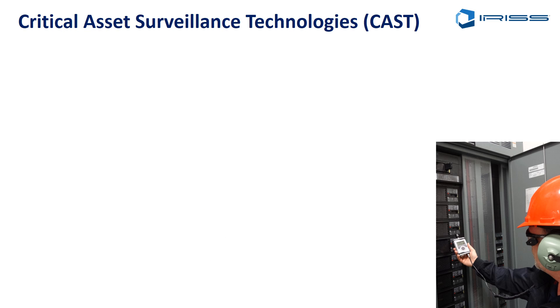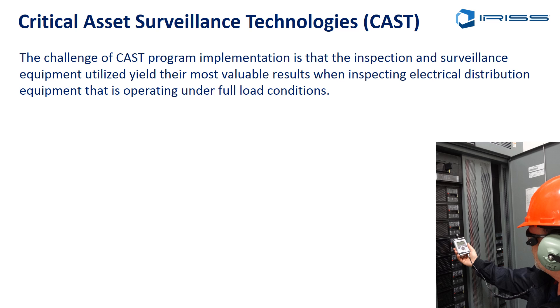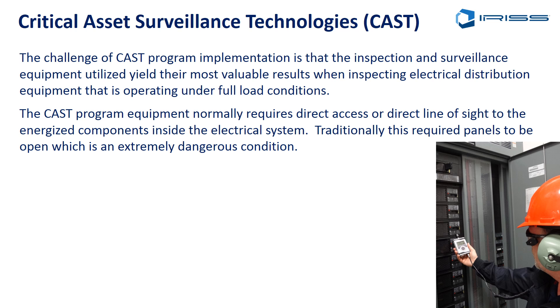There are a number of things we need to consider when utilizing a CAST program. First and foremost, we need the equipment under as much load as possible, because the equipment yields its most valuable results under load. An infrared camera won't show much with no load on the system — put some load on it, and the I²R high-resistance connection produces a lot of heat with current flowing through it, and we find problems much quicker. We also need direct access — an infrared camera can only measure what it can see.